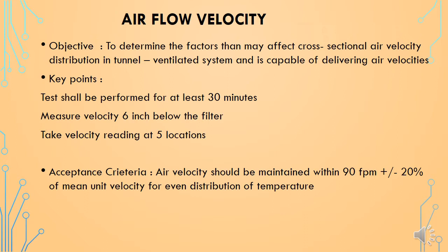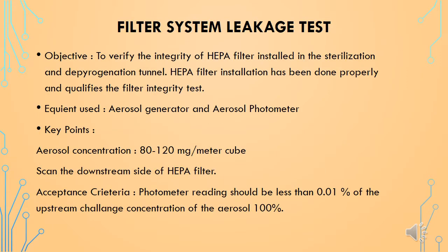The acceptance criteria for the air velocity check is that air velocity should be maintained within 90 feet per minute, plus or minus 20 percent of mean unit velocity, for even distribution of temperature.